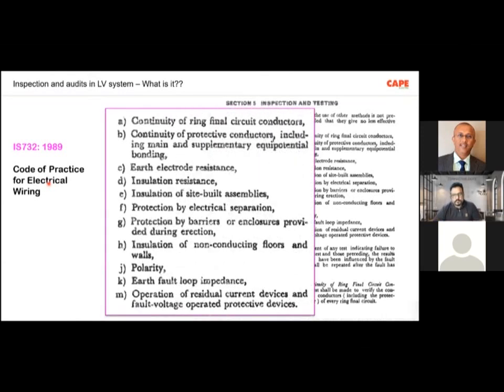Now the section 5 of IS 732, remember how many years back it is, 32 years back, has included inspection and testing of an electrical installation, which has A to M, different kinds of testing, a lot of things. I am only showing you the testings. Out of these, let us say for example, test number C, earth electrode resistance testing, except this particular test or sometimes the insulation resistance test, none of the other tests are made in an industry.